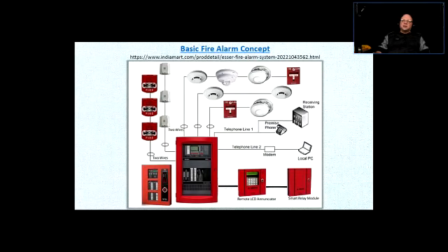If the fire alarm is connected to one of the zones, and that zone is named as a fire alarm zone, it will be programmed to be triggerable 24/7, so the security system doesn't have to be armed if there's a fire condition. If that zone is tripped, then things happen. It could be going into alarm, or it could be initiating communications with the monitoring station. So you can interface things back and forth.